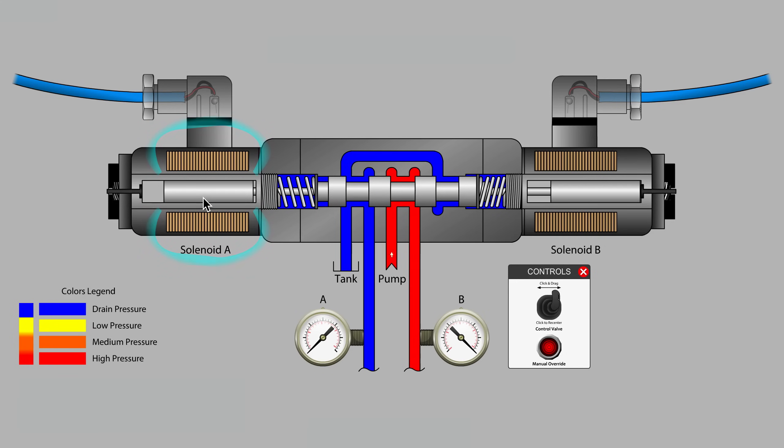The field pulls the armature in towards the center of the winding. The armature slides easily in a tube that is internally lubricated with hydraulic oil. The armature moves the pushpin, and ultimately the pushpin moves the valve spool. And now we see flow from the pump being directed to work port B.